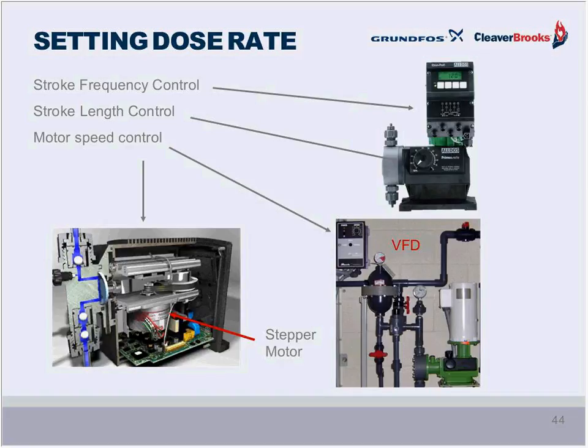With the stepper motor, it's a bit easier because we're simply setting the pump to a desired feed rate, let's say gallons per hour. So simply going to the pump and telling it the gallons per hour you want, that's all the setup there is. These pumps will use 100% stroke length, and so this variable remains constant. The motor is infinitely variable within the minimum and maximum allowable flow limits for each pump. It will make small rotations or steps over the course of one revolution. Movement can occur in various intervals and at various speeds. For example, it can have different speeds for the suction stroke than for the discharge stroke. These movement characteristics provide the ability to precisely control the amount of liquid injected and the time over which it is injected also. It provides accurate and reliable flow. There are a number of different methods for adjusting the dosing rate, and technology built into the different styles of pumps.